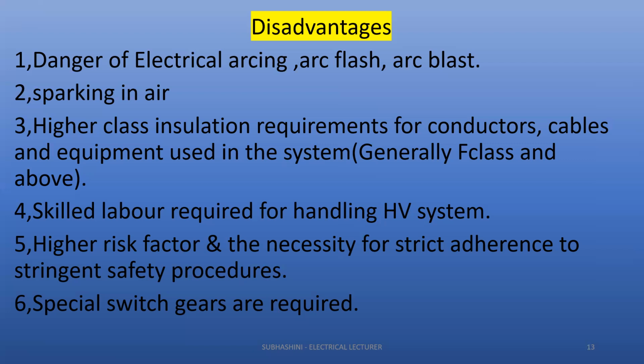Higher class insulation is required for conductors, cables and equipment used in the system. Generally F class and above has to be used for the insulation. We have different types of cable insulation, such as polyethylene and butyl rubber in the old version, and here we go for F class insulation for a high voltage system. Skilled labor is required for handling HV systems. The person must be experienced with HV connections, installation and maintenance, and must work with the proper work permit and other necessary actions. Safety is first. There is a higher risk factor and a necessity for strict adherence to the safety procedures. So the main disadvantage is the risk factor, and we have to follow the safety procedures properly.